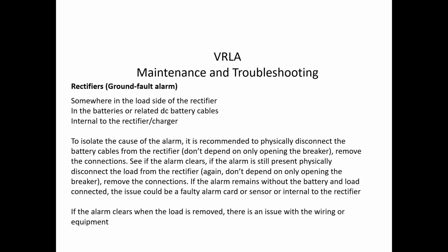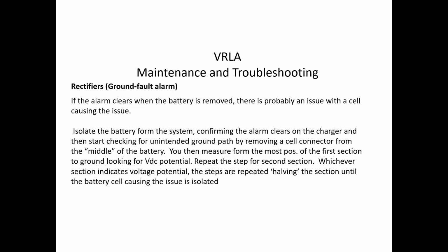But if you can, isolate the battery, take it totally out of service. Don't just open the disconnect, but remove the cables. See if the alarm goes away at that point. If the alarm's still present, then if you have the luxury, or at some time of a scheduled outage, remove the load from the rectifier and identify it that way. See if the problem goes away with the items as you're removing them. If you remove the load and your battery's not connected and the alarm's still present, well then it's within the rectifier.